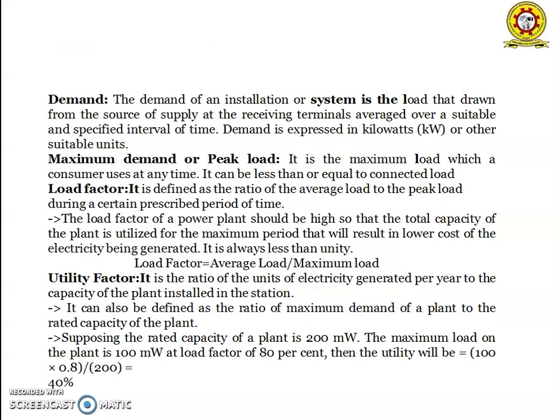Next one is the demand. The demand of an installation or a system is the load that it draws from the source of supply at the receiving terminals, averaged over a suitable and specified interval of time. Demand is expressed in kilowatts or other suitable units.